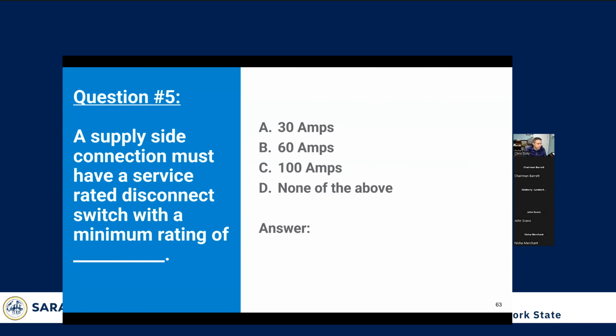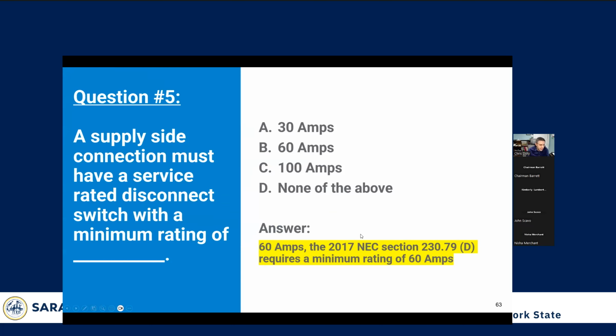A supply side connection must have a service rated disconnect switch with a minimum rating of which of these? And falling a little bit behind on time, so I'm going to zip right through this, but yes, the answers coming in mostly are looking good. It's going to be B, 60 amps. That's per the 2017 NEC code.